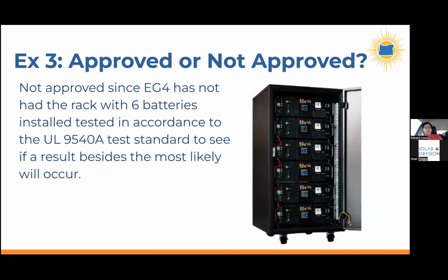All right. What about this example? I was disappointed to find out that, yes, this battery is UL 9540A tested as an individual server rack battery, but they have not done the test for 6 of these batteries stuck into a server rack and tested together. And so this configuration in the rack has not been 9540A tested. And even though, as I showed you in the report from the individual battery test, there's no flames emitted from 1 battery, so it should be safe, again, it doesn't matter. That's not good enough. You still have to test it.